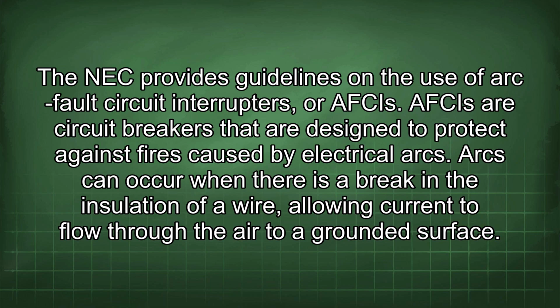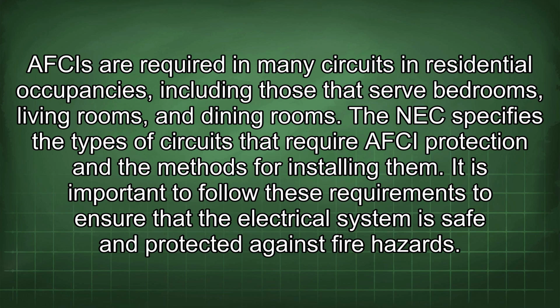The NEC provides guidelines on the use of arc fault circuit interrupters, or AFCIs. AFCIs are circuit breakers that are designed to protect against fires caused by electrical arcs. Arcs can occur when there is a break in the insulation of a wire, allowing current to flow through the air to a grounded surface. AFCIs are required in many circuits in residential occupancies, including those that serve bedrooms, living rooms, and dining rooms. The NEC specifies the types of circuits that require AFCI protection and the methods for installing them. It is important to follow these requirements to ensure that the electrical system is safe and protected against fire hazards.